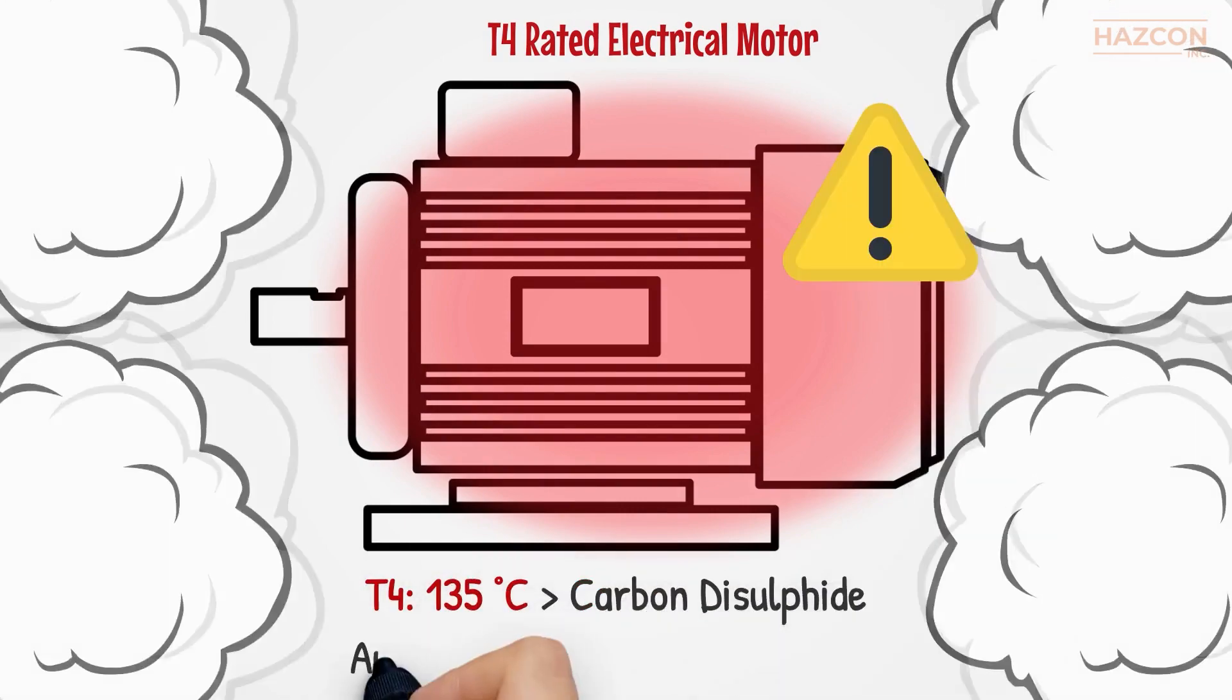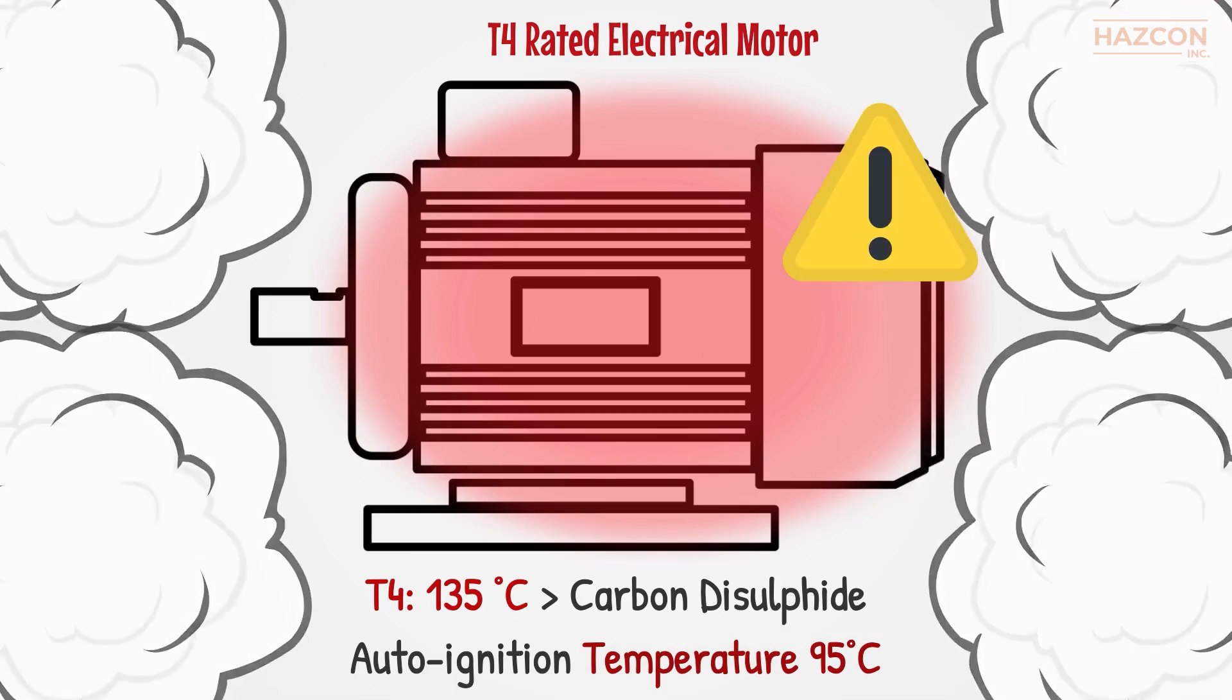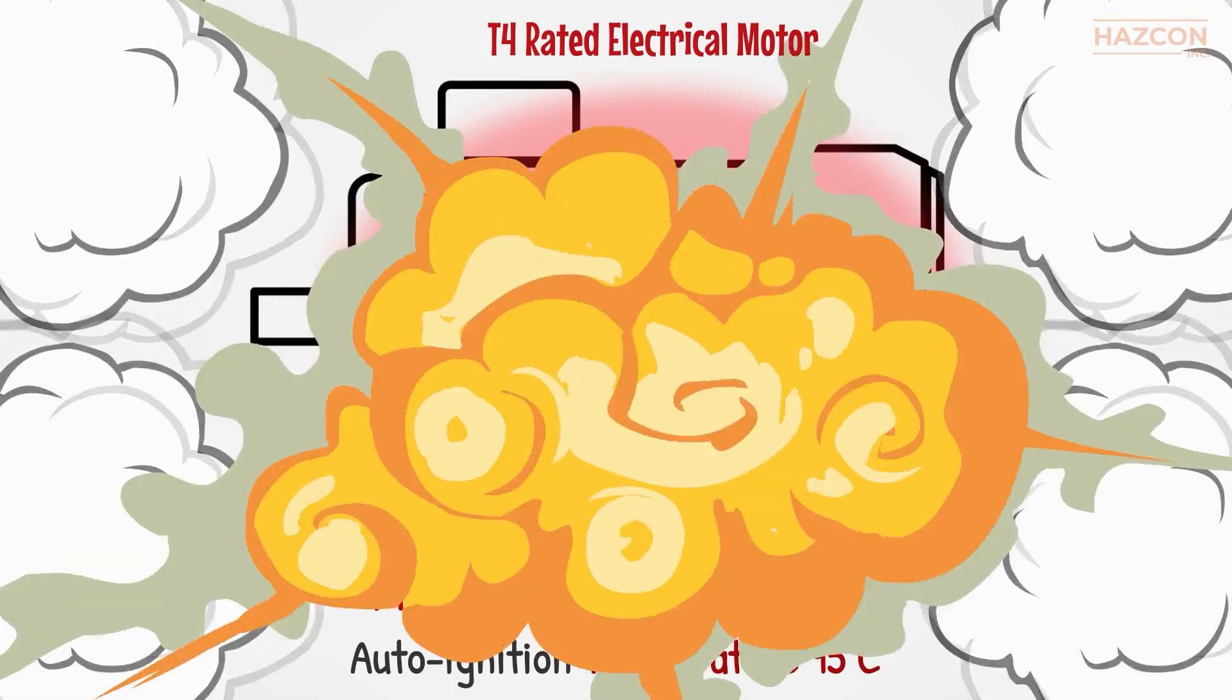If this motor were installed in a location in which carbon disulfide with an auto-ignition temperature of 95 degrees Celsius is present, the result would be an explosion.